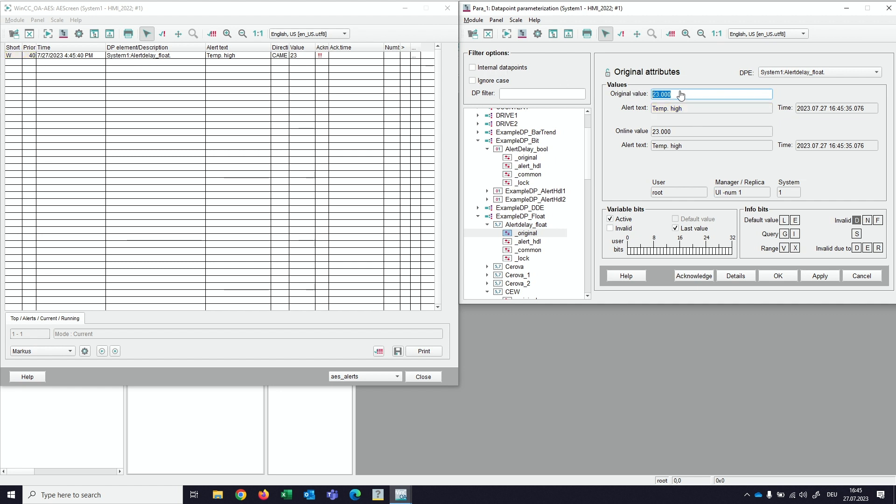Now when there is just a short peak over the limit and then we come back to the other range, there is nothing that happens. No matter how often, when the 5 seconds is not reached, nothing will happen. That's exactly the reason why we have the delay.